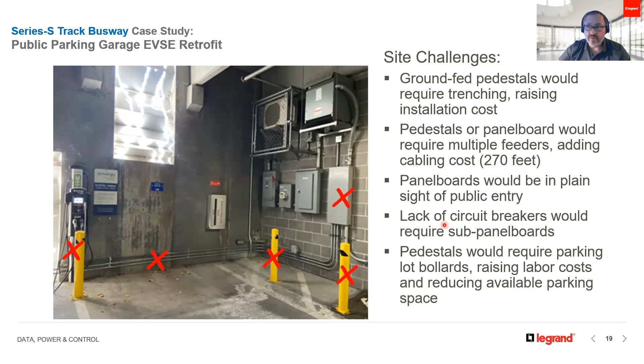So you start seeing all the different issues they were having here, and we're not even mentioning the non-electrical challenges. Just like Doug said, they had to shut down the elevator and make sure nobody got stuck in there, and they had to do it quickly. Also, if they were going to trench through concrete, they'd have to hire a geotechnical engineering firm to do infrared studies through the concrete, making sure there were no tension cables they could damage by drilling through. A lot of moving parts.